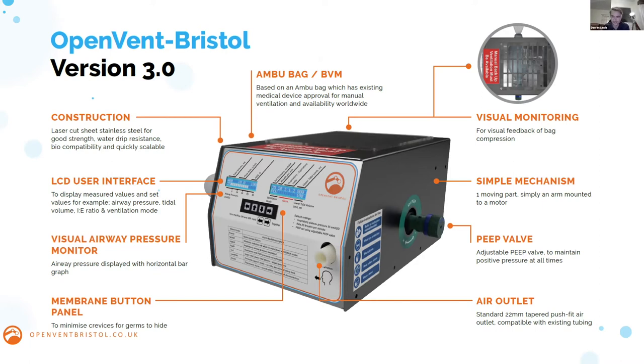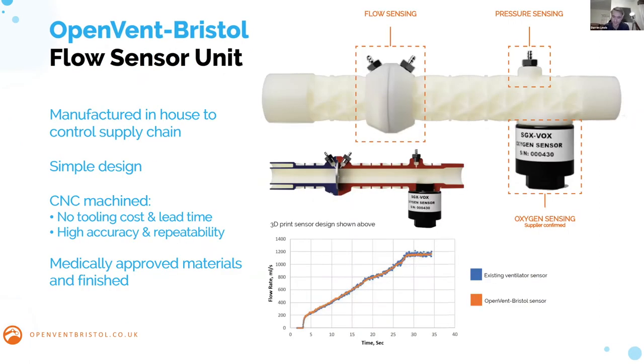One thing, and in fact the only thing we've created which isn't an off-the-shelf part, is the flow sensor unit, as Robert mentioned. For similar reasons that RespireWorks mentioned, these flow sensor units are quite scarce at the moment because they're only really available to those existing manufacturers of ventilators. So the availability is quite unpredictable, and the reason we've made our own is to control our supply chain.